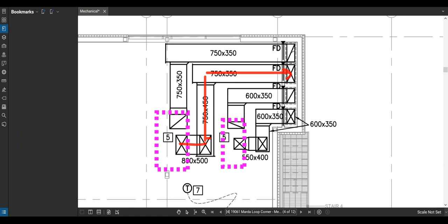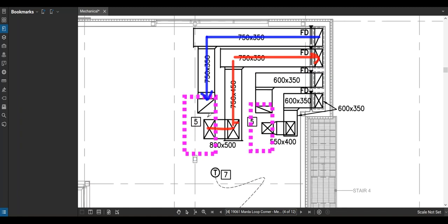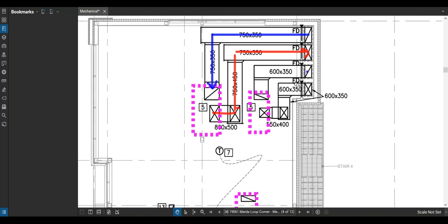The return air for this unit is right here. When you're looking at return ducts in the vertical, they have one line through them. So there's a return duct coming up from the main floor — at the ceiling of this tenant — going across and then up into that rooftop unit above. That one unit is not serving this tenant on the second floor at all; it's dedicated to a tenant on the main floor. The other rooftop unit here is kind of the same idea, with supply coming down and return going up. Neither of these units are serving the second floor tenant space.